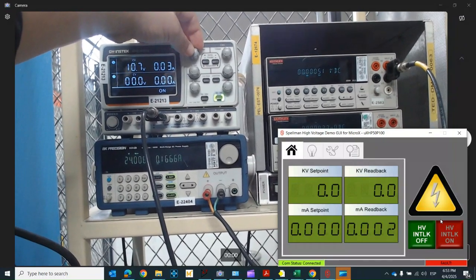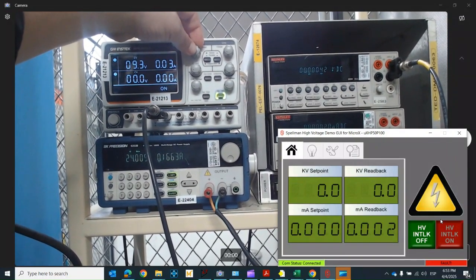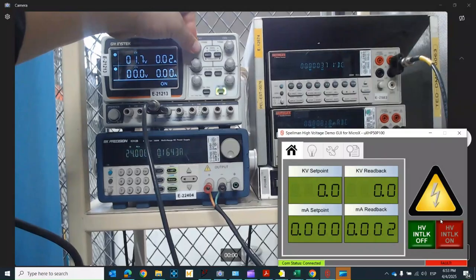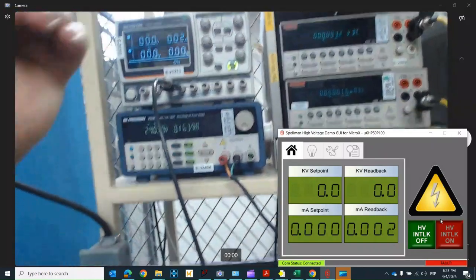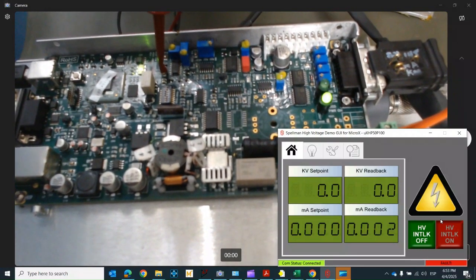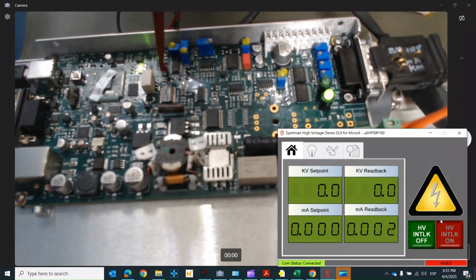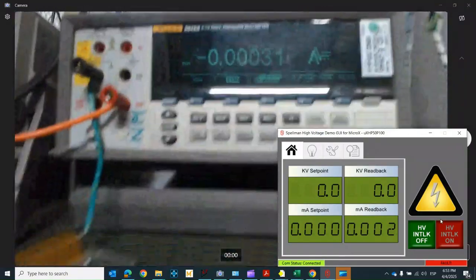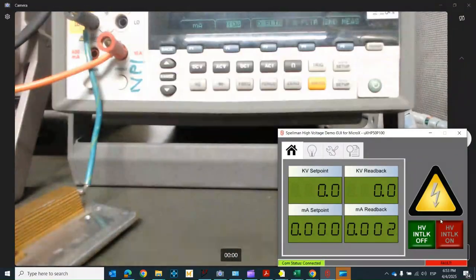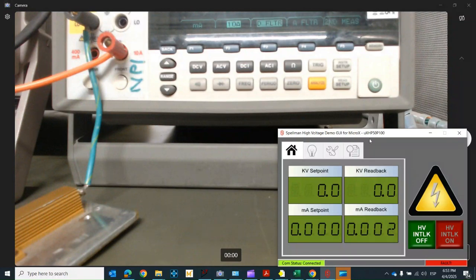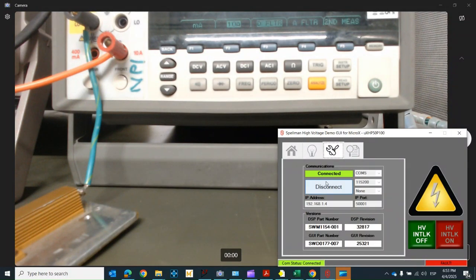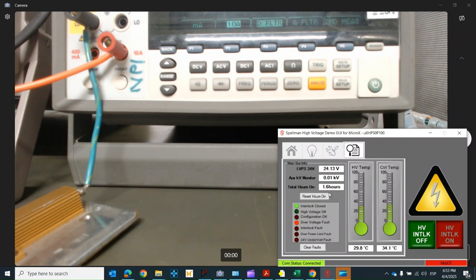It should be equal to or less than 6% above the rated voltage, which in this case occurred without issues. We will also confirm that the high voltage on LED turned off and that the power on LED is blinking. There also should be no output present, and the over voltage fault indicator in the GUI should be on. It can also be noticed that even when attempting to turn on the interlock without clearing, the faults will result in the unit not responding.